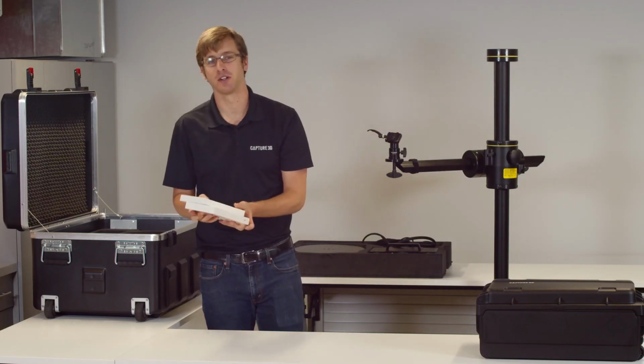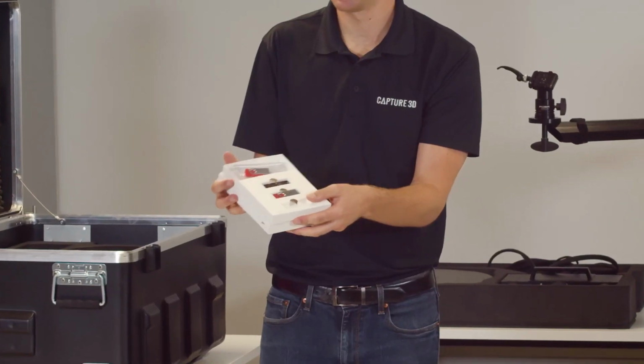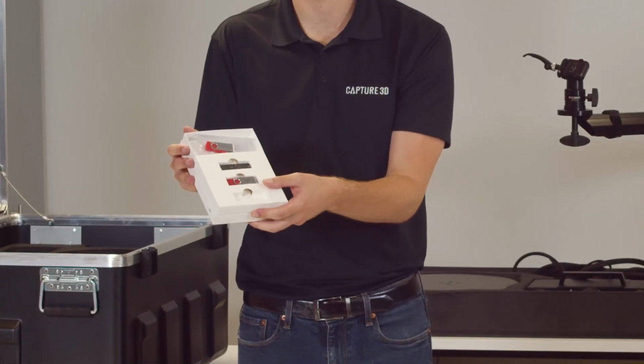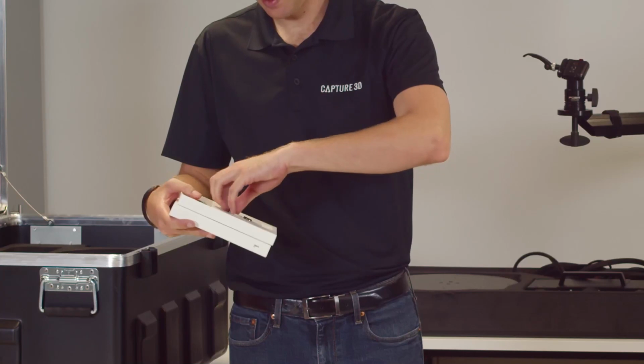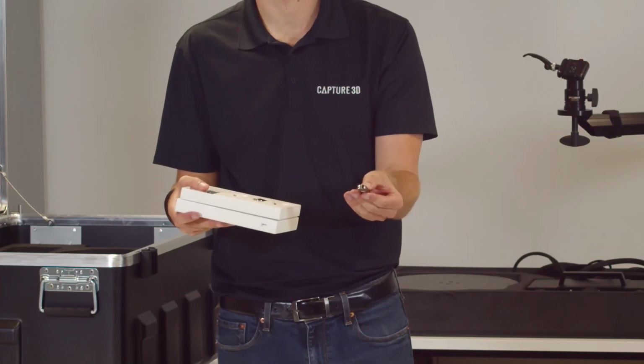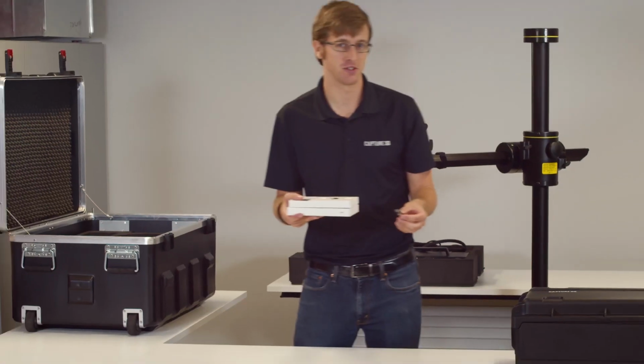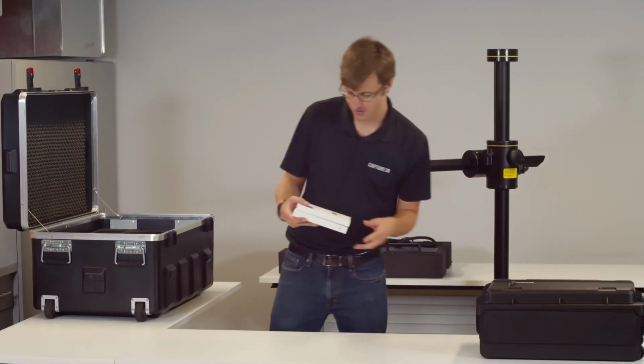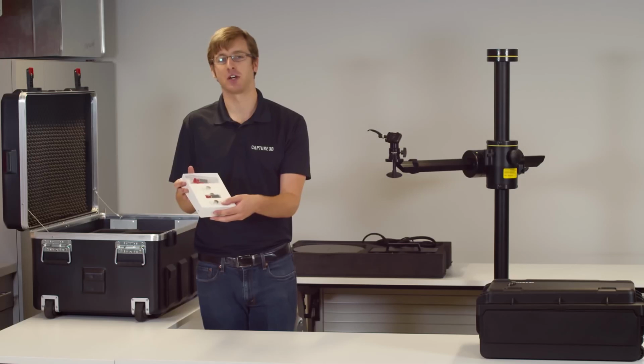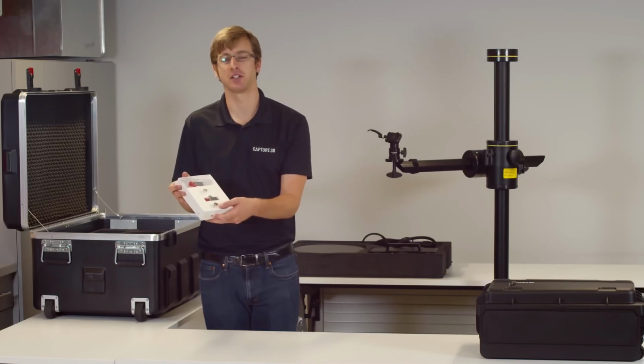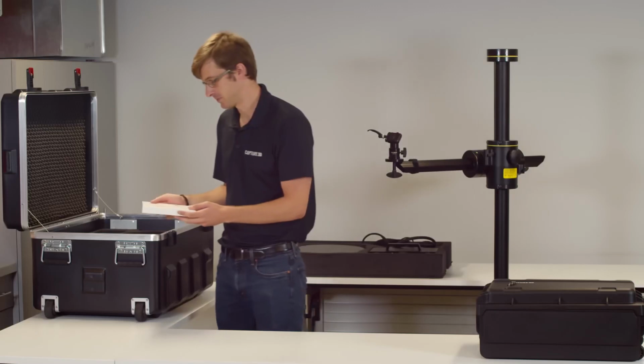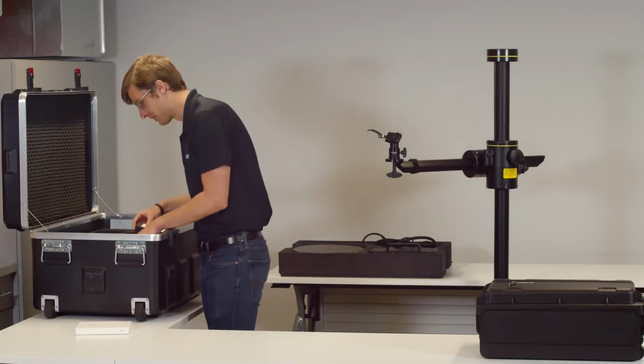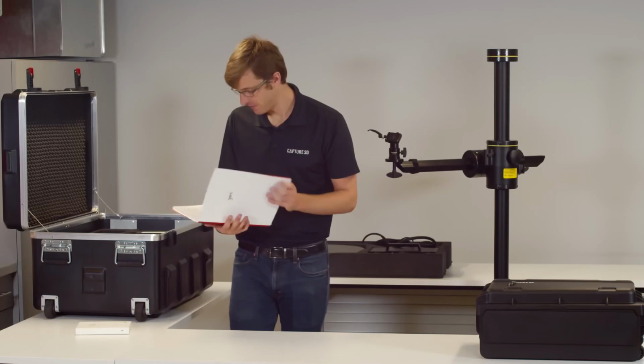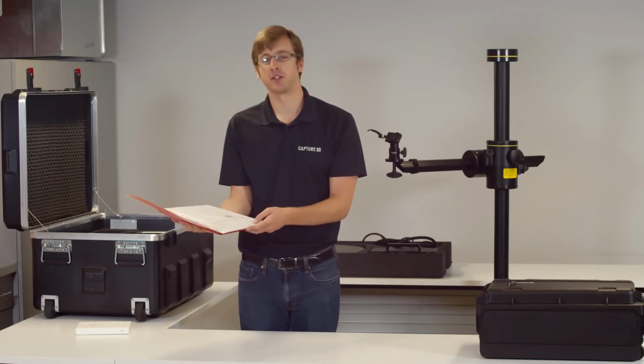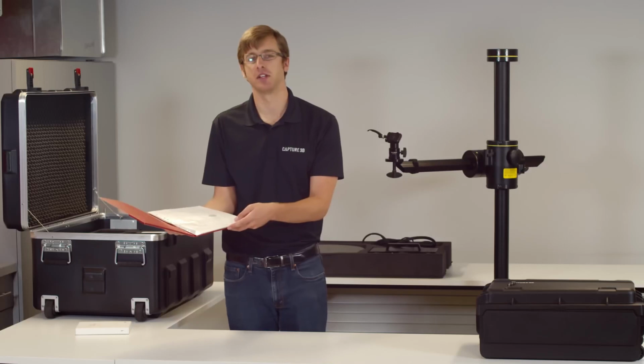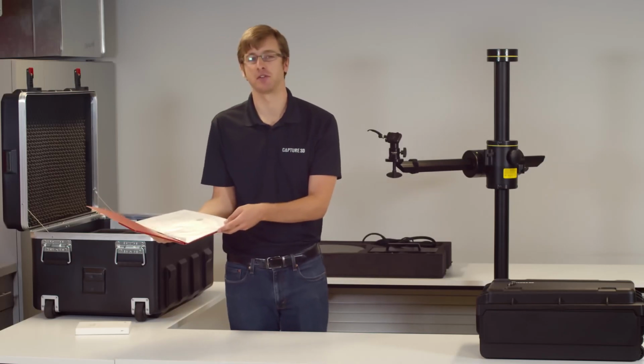And first up for the software, I see we have 3 USB drives included. And these will have instructions for the installation and where to find support for the system. The license dongle will let us run the 2020 GOM Suite. So we're going to use this later, and I'll leave it with the controller. We also have information about the calibration artifact and the VDI accuracy test for the sensor. In this folder, we have more traceability information about the calibration artifact and the VDI test. We have the information for all the measuring volumes.